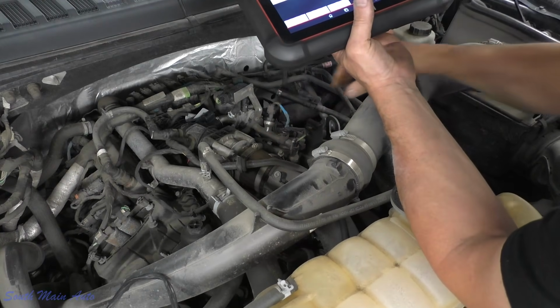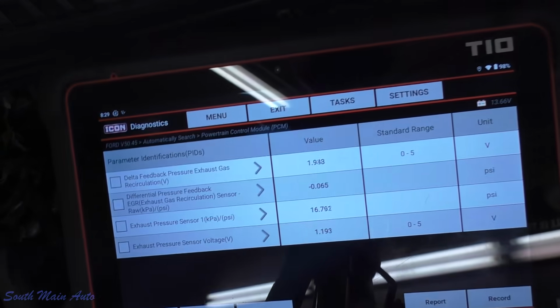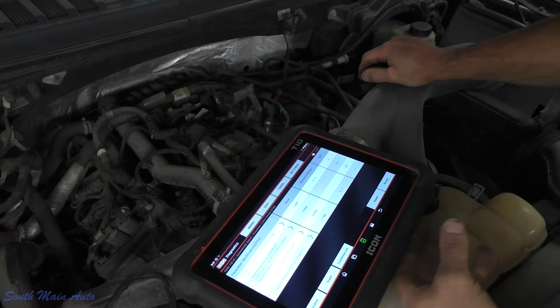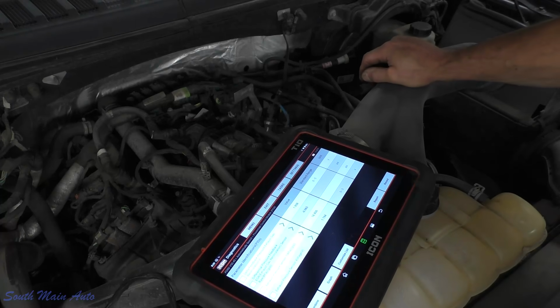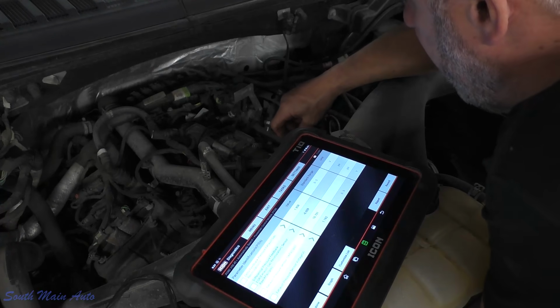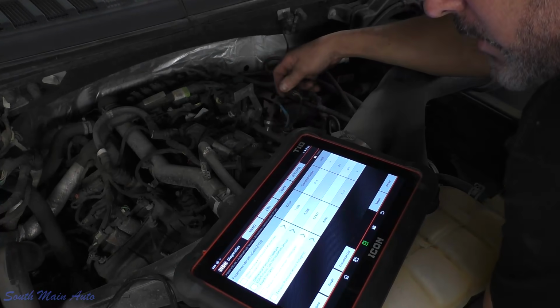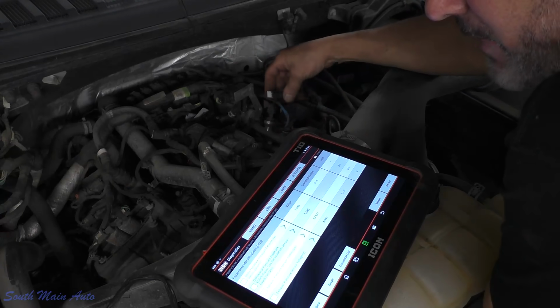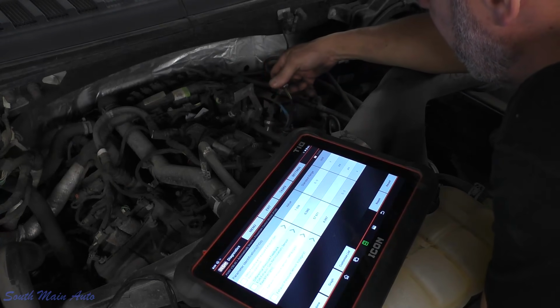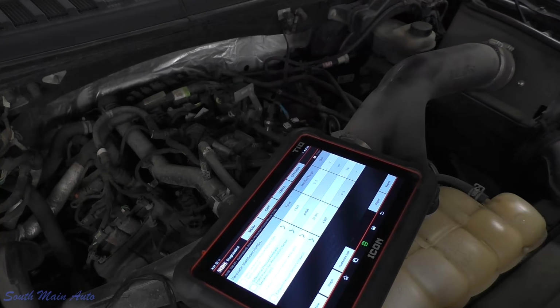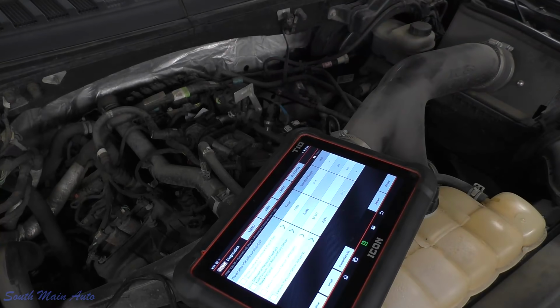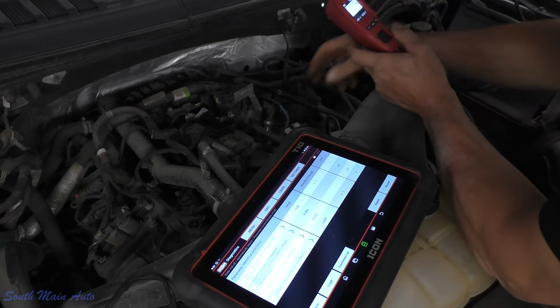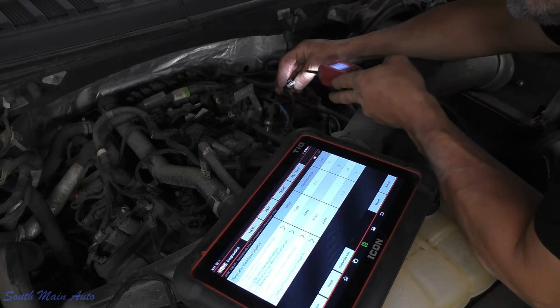I plug it back in, and we're at almost 17 PSI. So we're looking at a skewed sensor. Now we can do a very quick bypass test on it. We know we have our 5-volt bias coming down our signal wire, because that's what it is, open circuited. Let's check, let's just grab the prober. Over here, so two of these wires, the old needle in the mouth trick, two of these wires should have 5 volts.